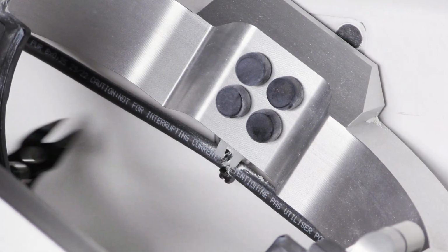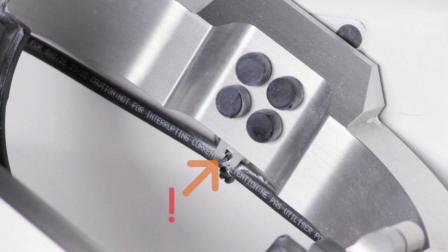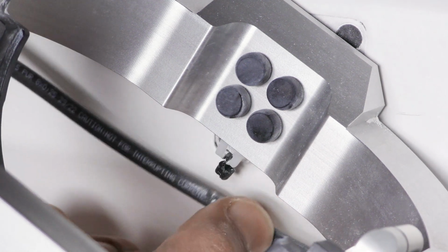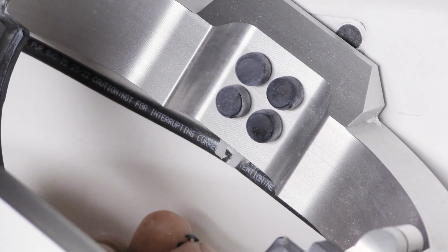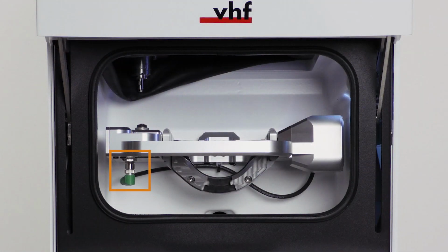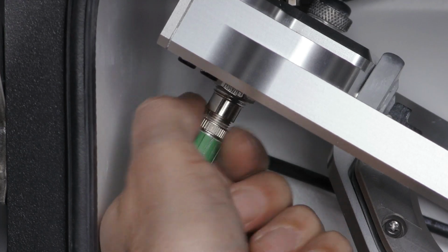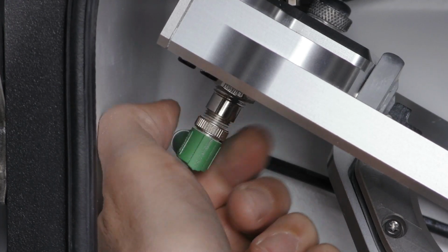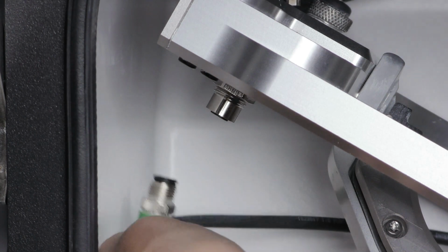Carefully cut the cable tie with the wire cutter. Notice: do not damage the A-axis cable. Pull the cable downwards out of the fixation. Remove the cable tie. Unscrew the A-axis cable of the AB axis module. Open the knurled nut on the lower left side of the AB axis module. Pull the cable downwards at the plug.